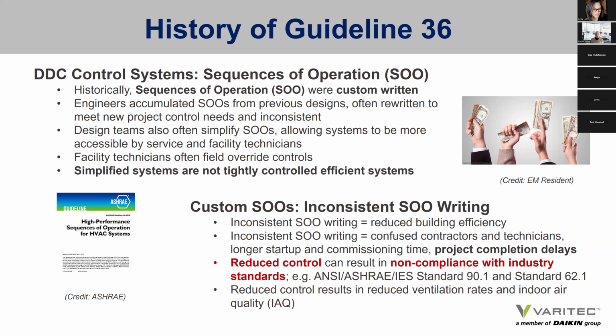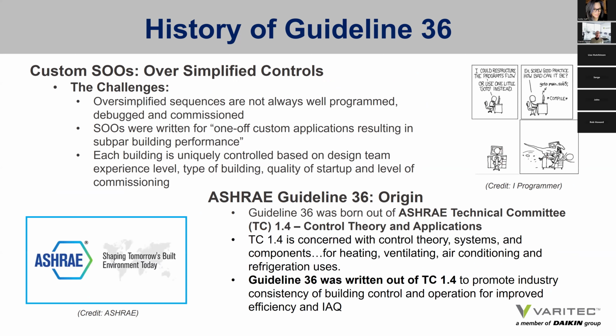So reduced control in a building can also result in non-compliance with industry standards, such as ASHRAE Standard 90.1 and ASHRAE's ventilation standard 62.1. So reduced control results in reduced ventilation rates and indoor air quality. The challenges with simplified controls are that oversimplified sequences are not always well programmed, debugged, and commissioned. They were written for one-off custom applications, resulting in subpar building performance historically.